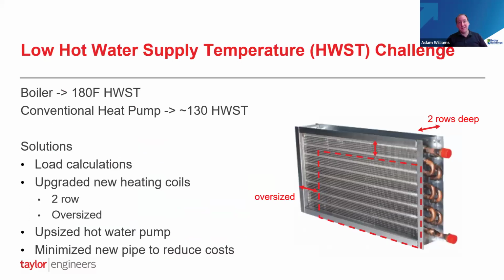Okay, so the first thing, low hot water supply temperature. As Kyle mentioned, boilers generally can meet about 180 degree hot water supply temperature, and many systems are designed for that high of a hot water supply temperature going through the pipes and the coils. So the piping and the coils are sized to accommodate that. The heat pumps generally can do about 130. There are some modern heat pumps that can do 140, but beyond that, that's generally what most of the current technology is doing, about 130 degree hot water supply temperature.